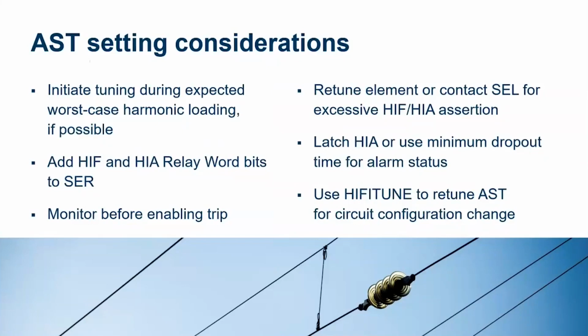If possible, it's best to initiate your initial tuning in the cases where you expect worst case harmonic loading. And once again, we recommend to turn it on and watch it and see if it asserts, how often the elements assert. And if we see excessive alarms, excessive fault bits, and you're able to determine these are definitely not associated with high impedance faults on the system, of course, you can retune or reach out to us, and your local SEL application engineers are happy to discuss and help out with that.